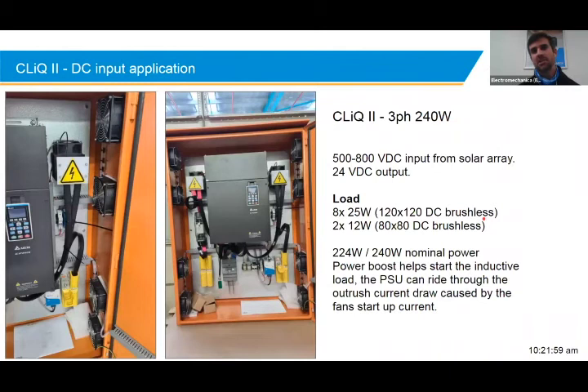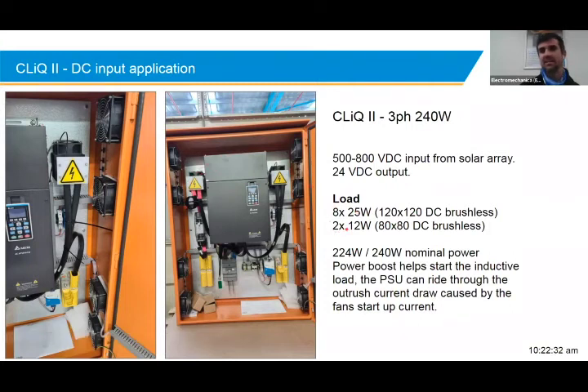Just an application on the CLIQ2. Here we've got an application where the drive is used as a solar drive, so there's no mains voltage connected to it. Direct connection from the solar array between 500 and say 800 volts DC. The solar array is connected directly to the CLIQ power supply here on the bottom, and the CLIQ drives 1, 2, 3, 4, 8, 10 fans. There's another 2 over here.